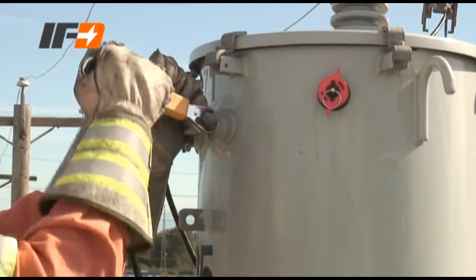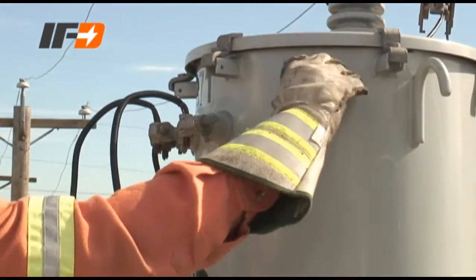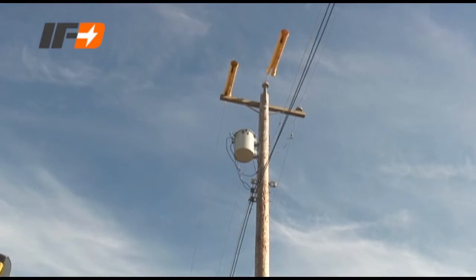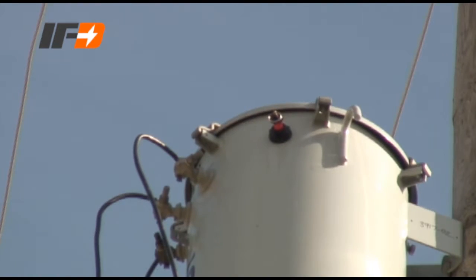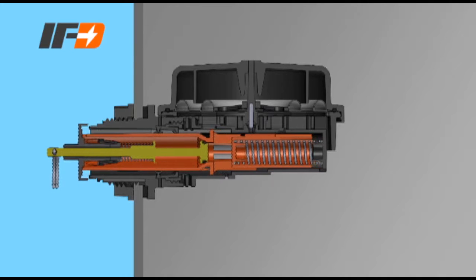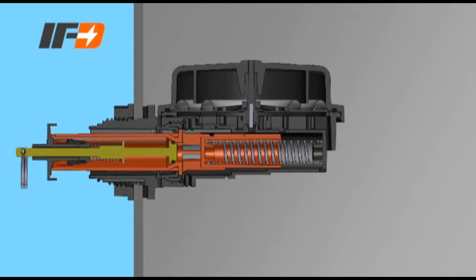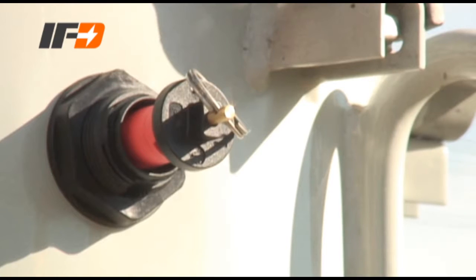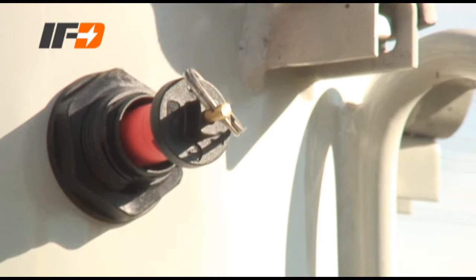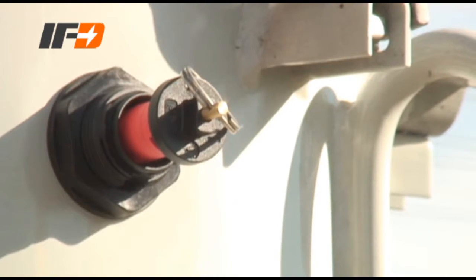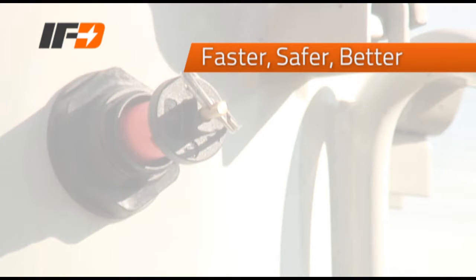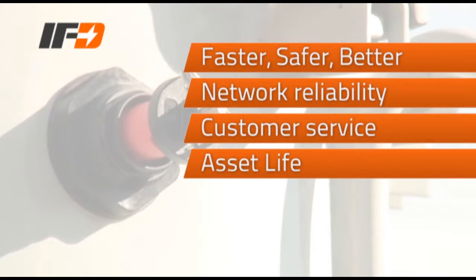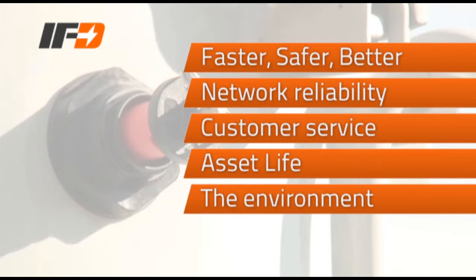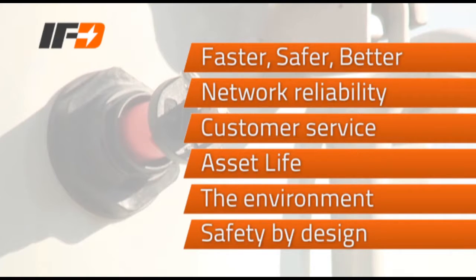To identify faulted transformers and enhance line worker safety, IFD Corporation developed the Internal Fault Detector, or IFD. The IFD sensor is a mechanical device requiring no electrical connections. The IFD provides line crews with the reliable information they need when troubleshooting distribution transformers. The benefits are, it's faster and safer for line crews to restore power, improve network reliability and customer service, extend asset life, avoid environmental damage, and create a safer job environment.